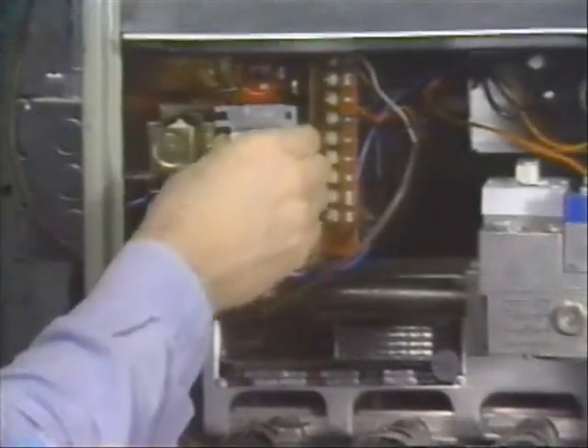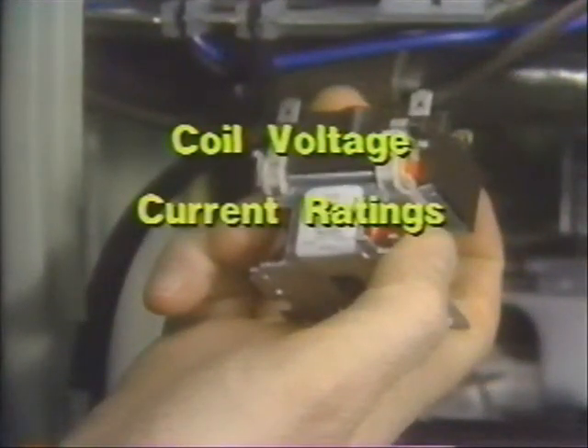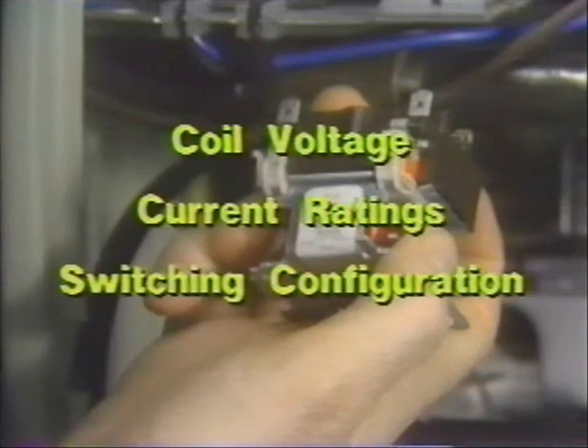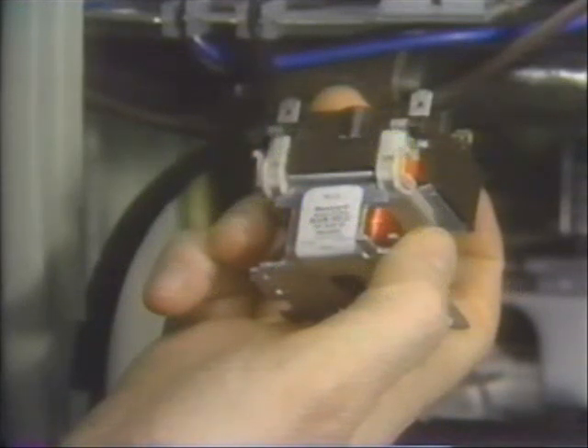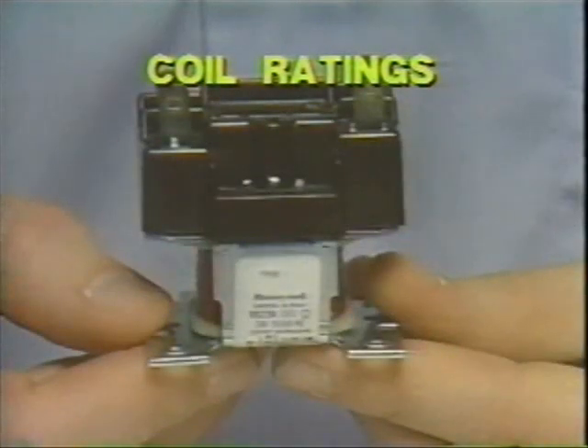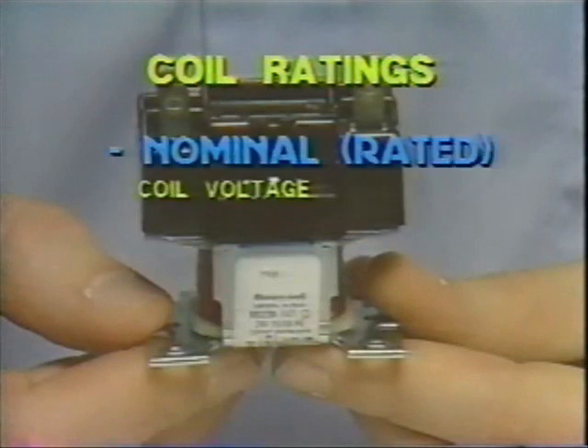review some relay ratings. As a rule, when selecting a replacement relay, the only things you have to know are coil voltage, contact current ratings, and the switching configuration. But there are a few other ratings you should be familiar with. Coil ratings describe a coil's characteristics as a user of electricity, because a coil is an electrical load in the control circuit. Nominal, or rated voltage, is the rated voltage of the coil. And in 95% of all applications, that's the only coil rating you have to know.